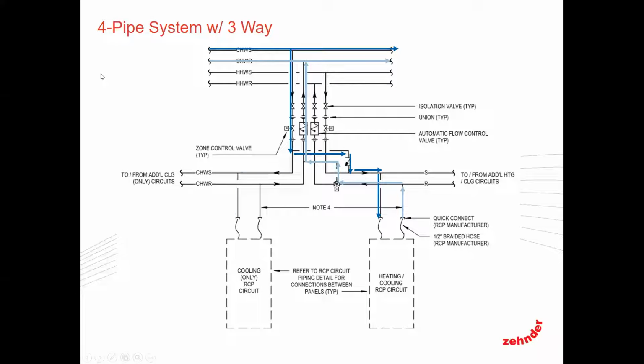And in this case, I actually have a secondary flow here that allows the chilled water into my cooling only loop, and then passes back into and mixes in with that return from the other circuits. When we switch over to heating, same thing happens. The 2-way control valve opens up on the hot water supply side, goes through my heating only circuit, and then the 3-way valve diverts it back into my hot water loop.